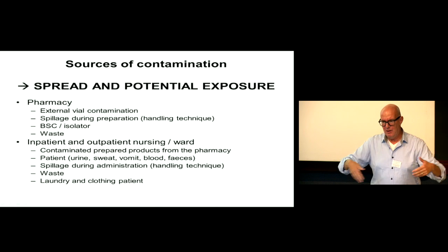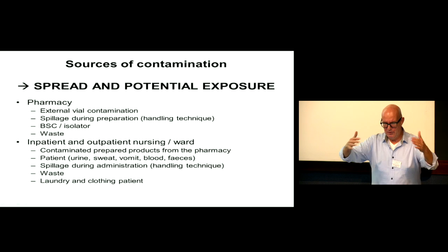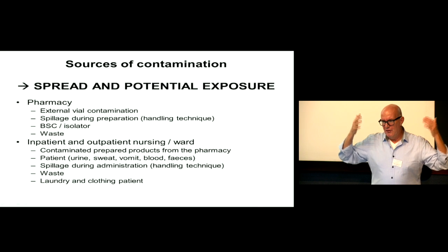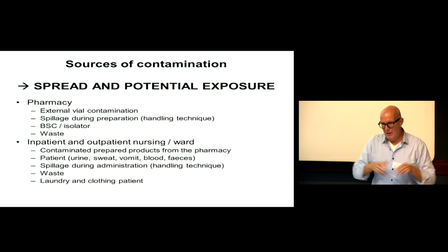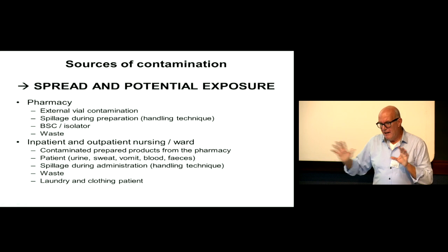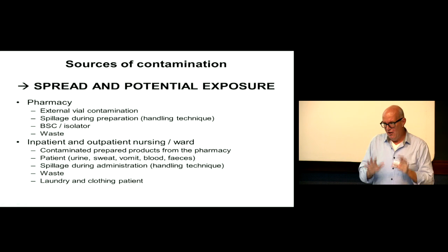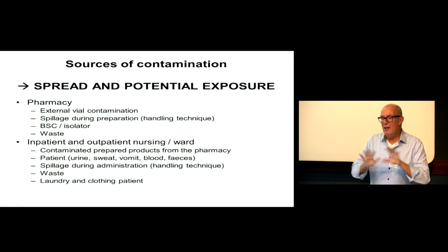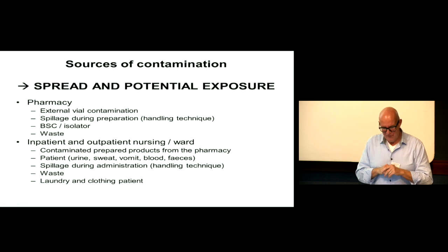If you take a cabinet with an airflow and you put your hands in, you always disturb the airflow, so there is always airflow going out. So you can be exposed to that. It's the same with an isolator. If you open the isolator at the end to take products out, you can be exposed there. So isolators and cabinets are not designed to protect you. They do a little, but they are not designed for it.